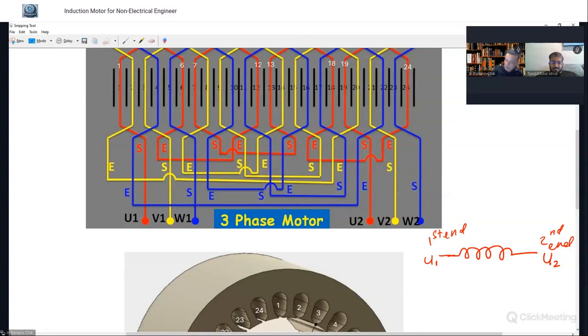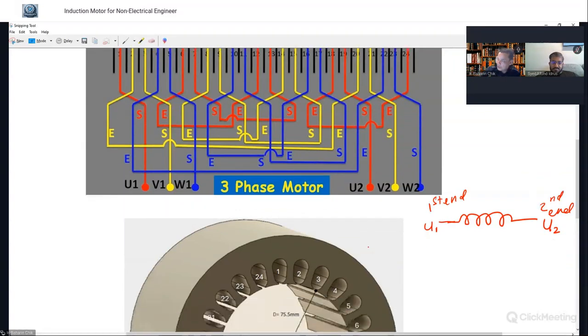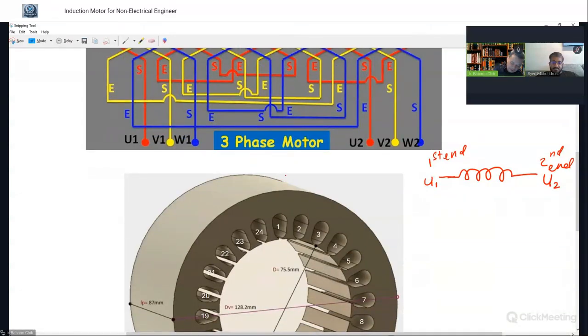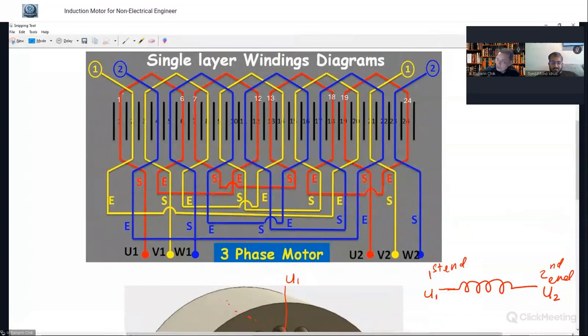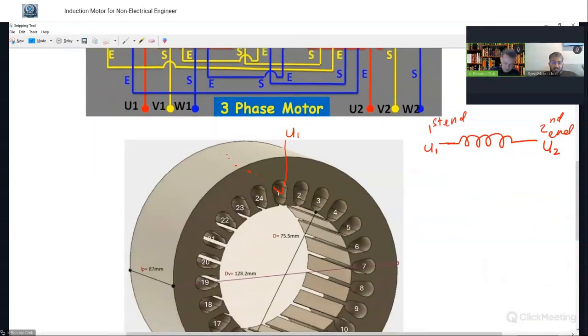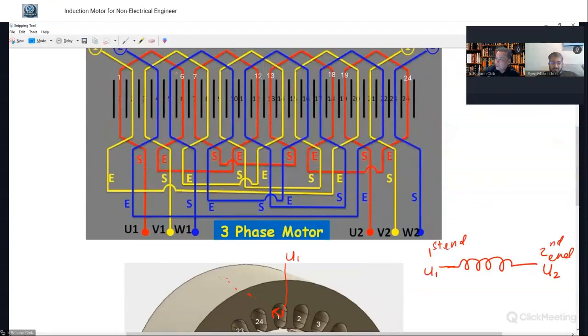Now what we are going to do is to wind it. For example, if I take this as U1, I put the winding inside, and it goes all the way to the back. Then it turns and goes inside slot number 6. Now we have the winding going inside, and at slot number 6 it is coming out. Now from slot number 6, it goes to slot number 12.